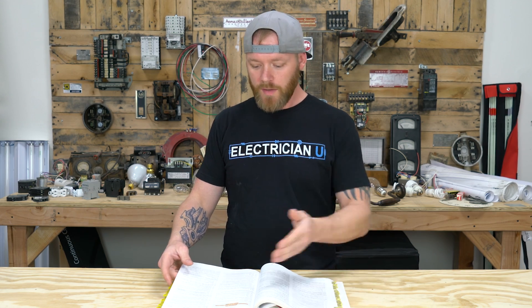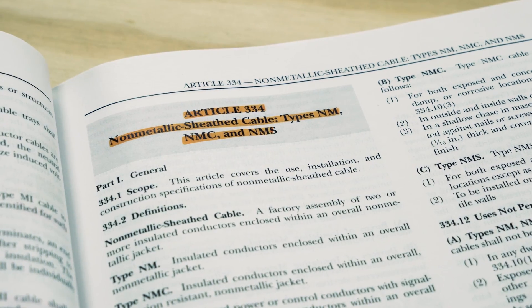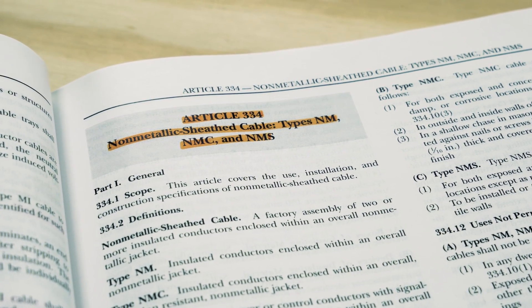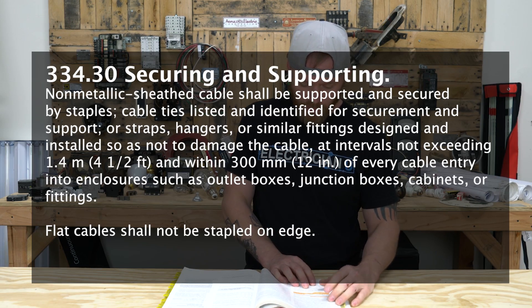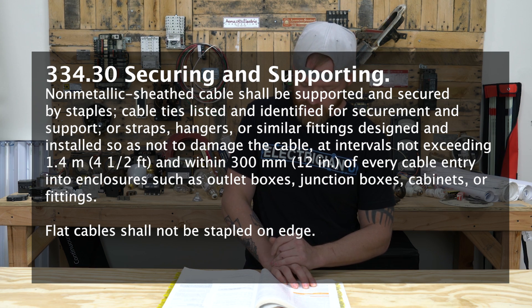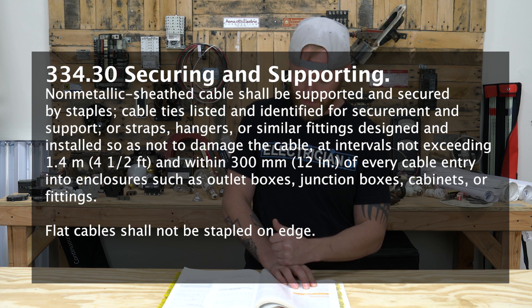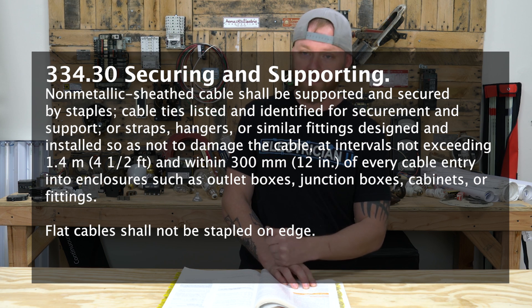If we go into the code, into Article 334, where it talks about non-metallic sheath cable — under securing and supporting, non-metallic sheath cable shall be supported and secured by staples, cable ties listed and identified for securement and support, or straps, hangers, or similar fittings designed to and installed so as to not damage the cable, at intervals not exceeding 1.4 meters, or four and a half feet.